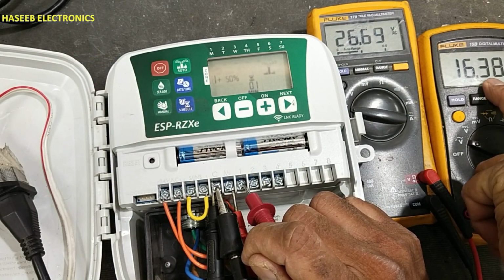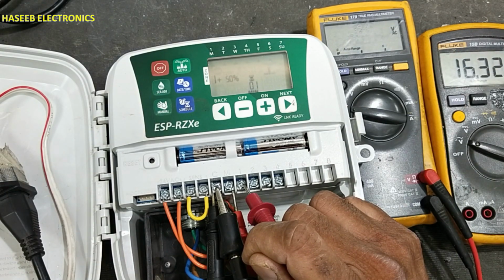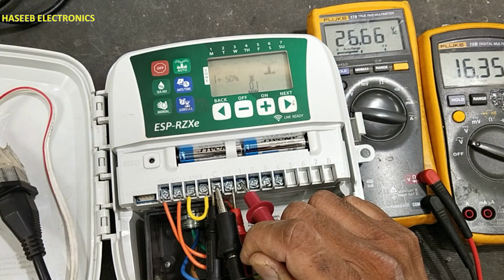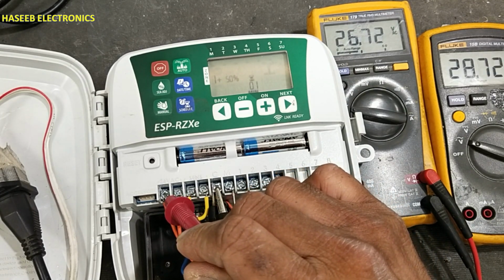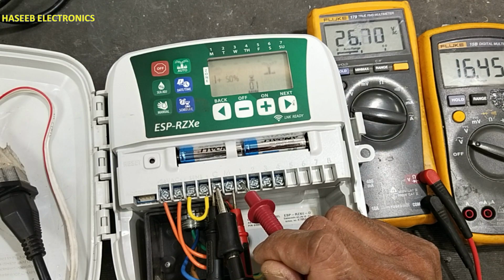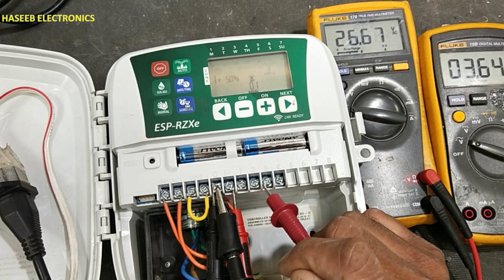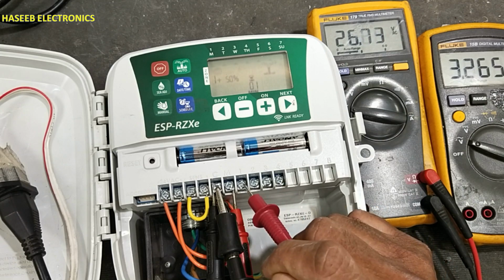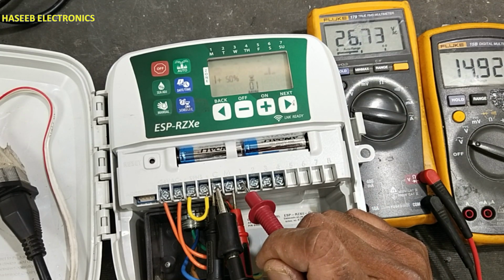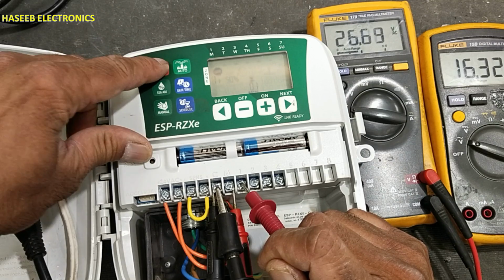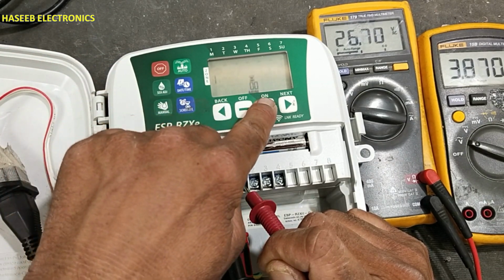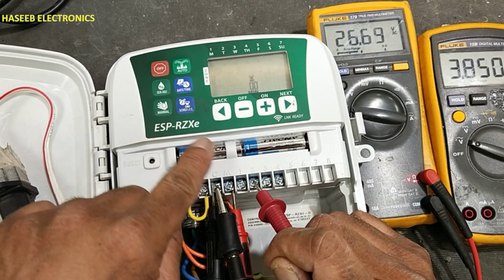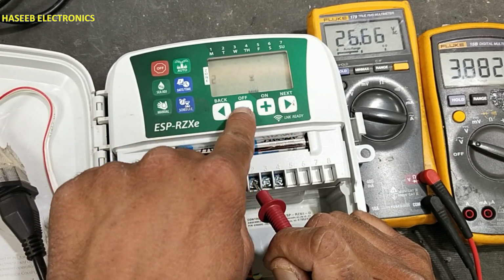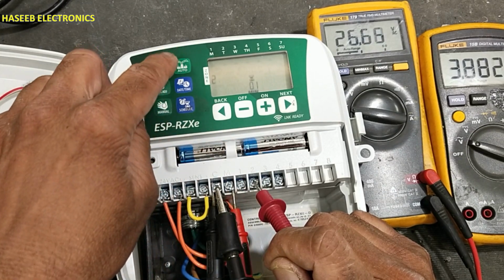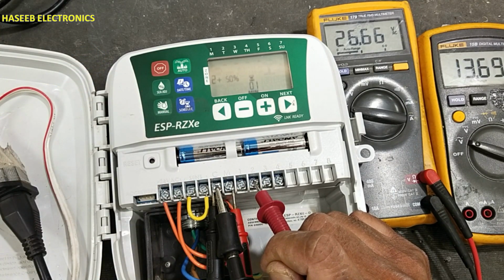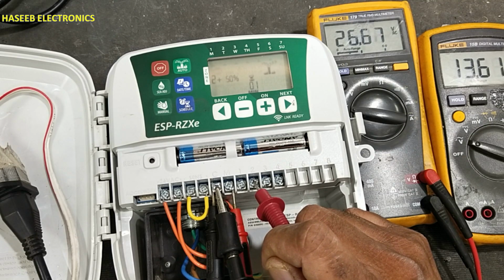We can see it is providing 16 volt and the master valve is providing 26 volt. 16 volt is not acceptable. It must provide 28 volt. Station number 1 is low, 2 is low, 3 is low, 4 is low. Okay, let me select station number 2, manual, for 1 minute. Station number 2 has the same, 13 volt, so it is not good.